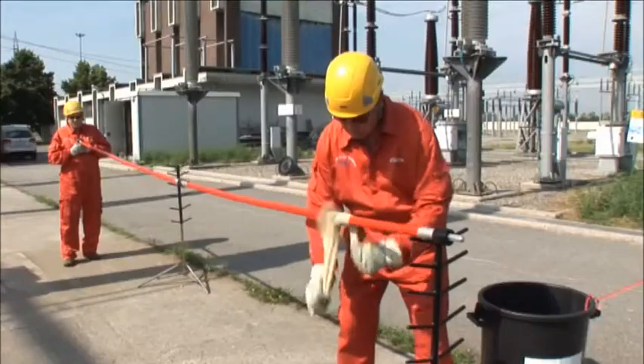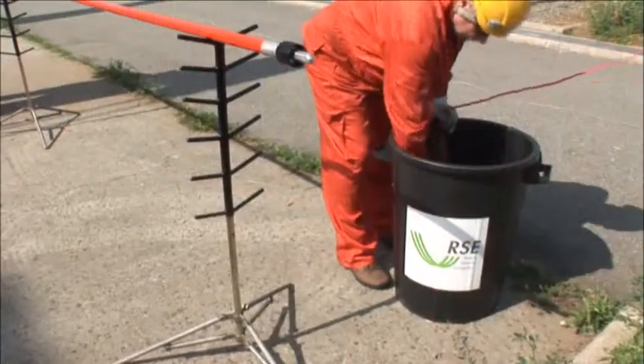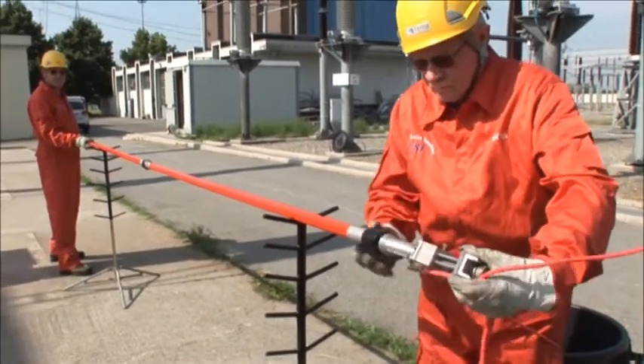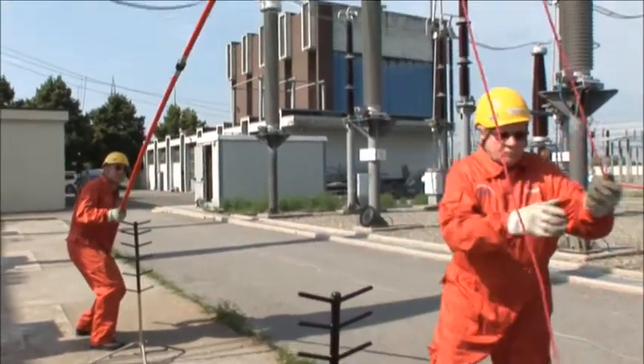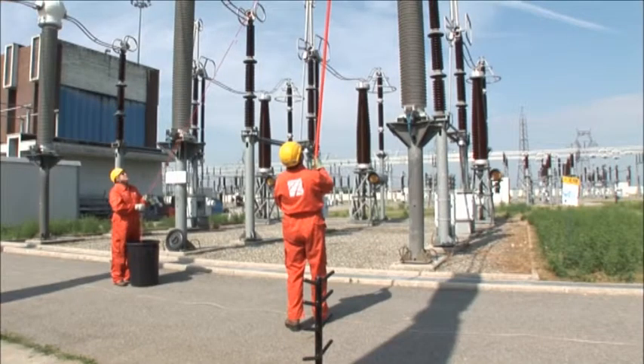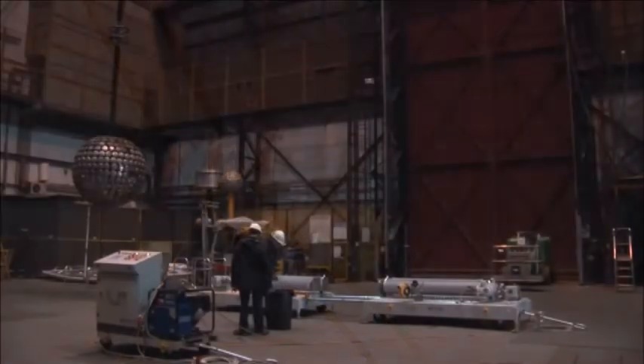To measure voltage, it is necessary to insert additional equipment. The voltage sensor is installed between a live line and ground, draining a non-negligible current and thus generating an electric arc, a phenomenon which, if not controlled, can be harmful to the equipment and people performing the measurements. It is therefore necessary to use a disconnector switch, a piece of equipment in common use, which, however, is normally resident in a network point and is not easily removable or transportable.